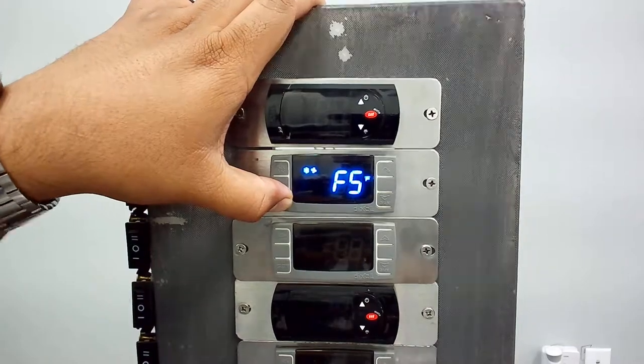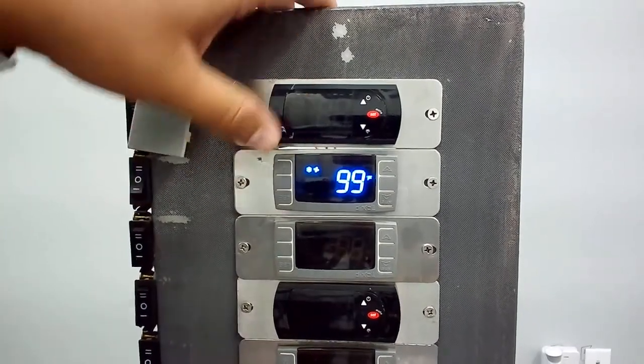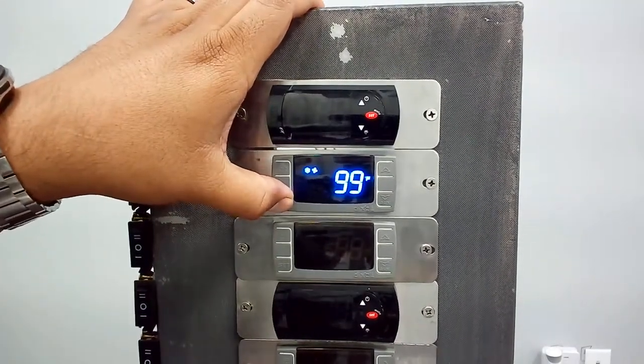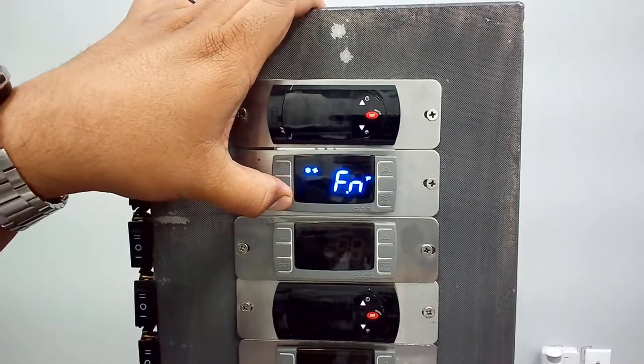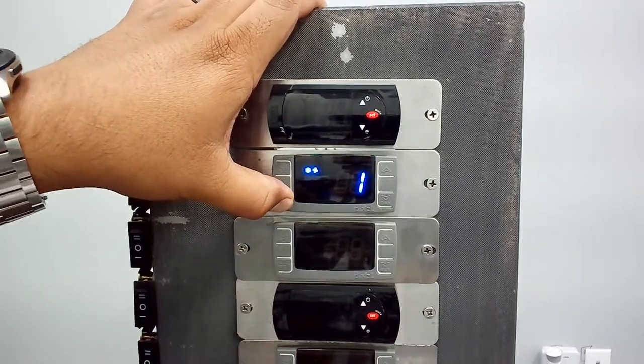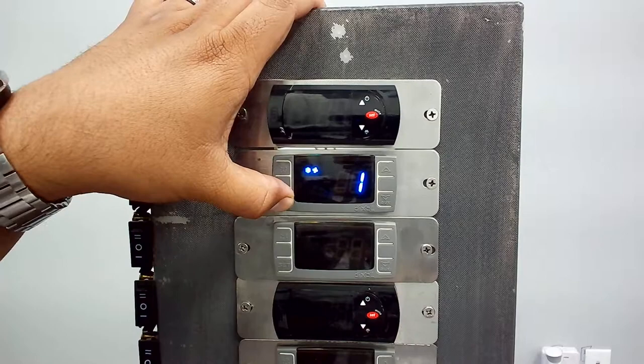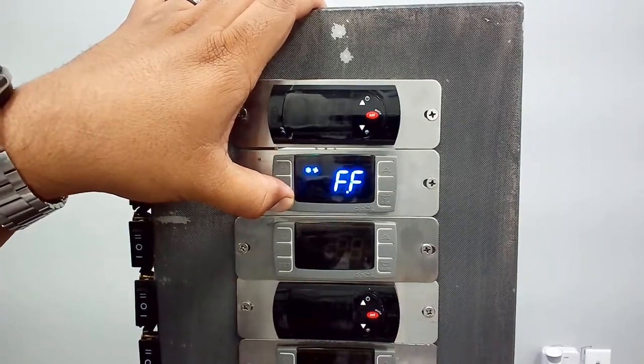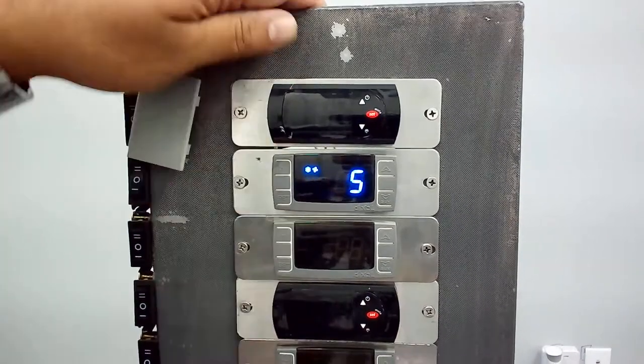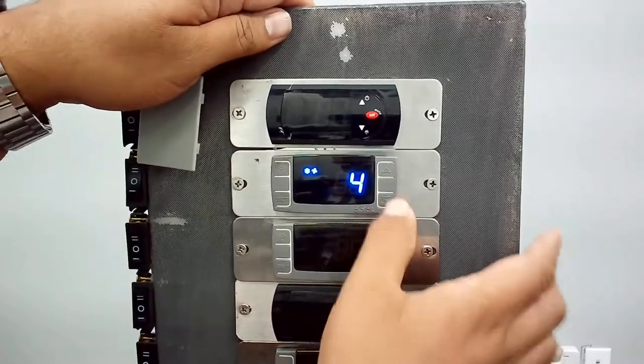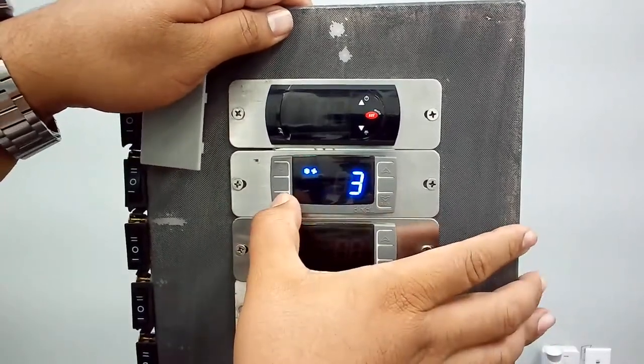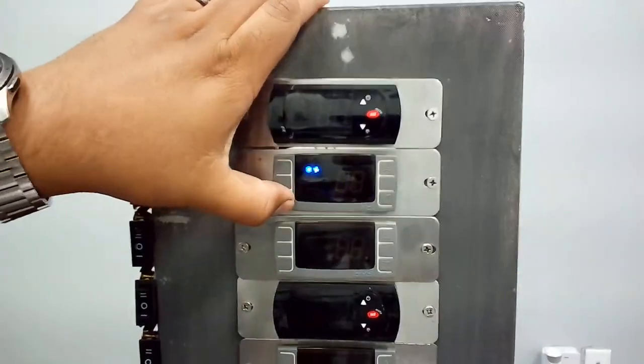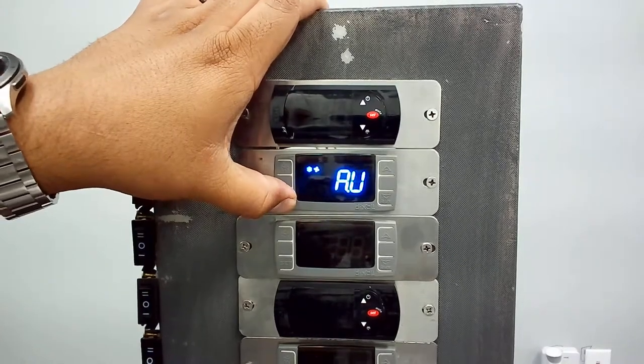F5, that's going to be the temperature for the fan stop, should be set to 99. This is regardless of unit. FN should be at 1, again, no matter what kind of unit it is. FF, it's going to be 3 rather than 5. And once again, that locks it in, moves on to the next one.